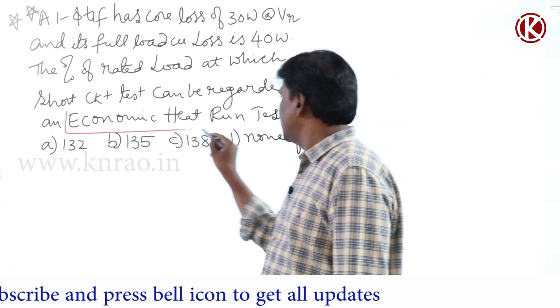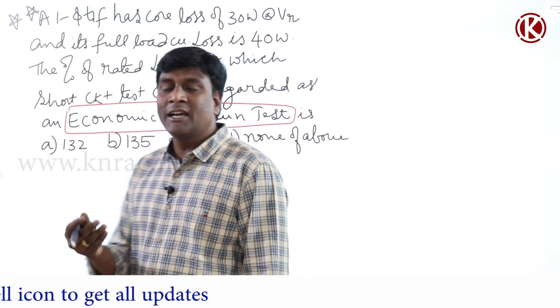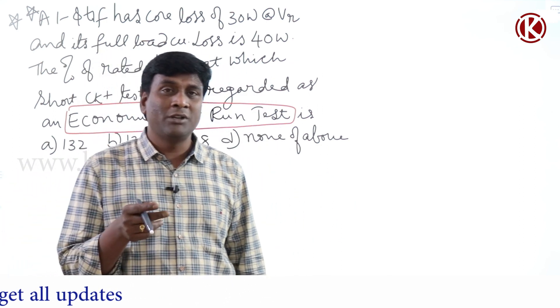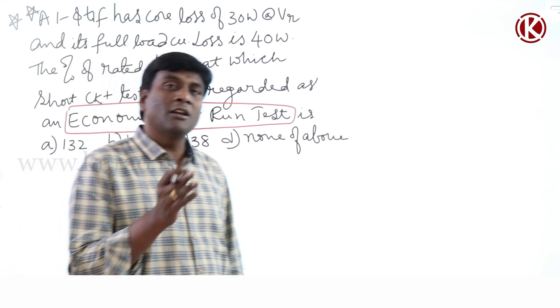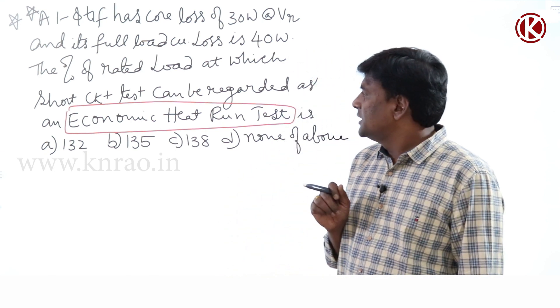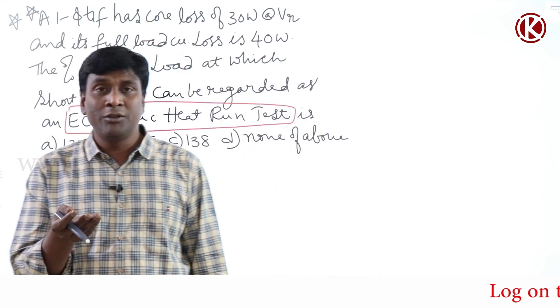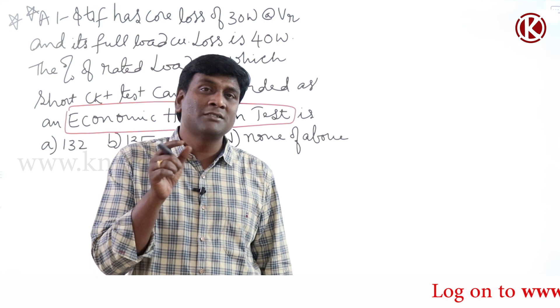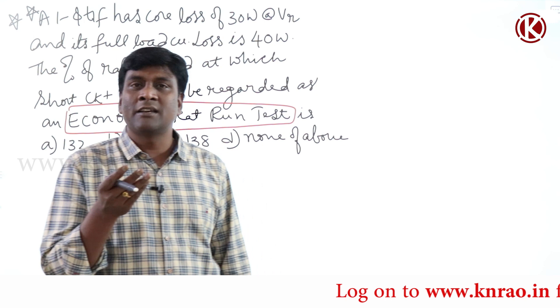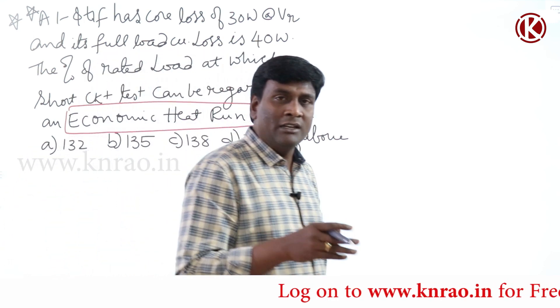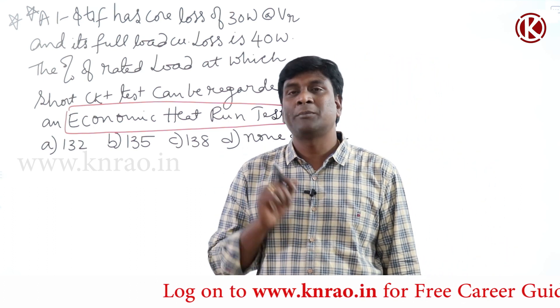We should understand what is meant by economic heat run test, and why economic heat run test is possible in short circuit conditions only, not in open circuit conditions. If you think of the short circuit test, we know that SC test can be conducted at any current value with any non-zero frequency, because SC test is used to find series branch parameters, and those series branch parameters are linear — not like non-linear shunt branch parameters.